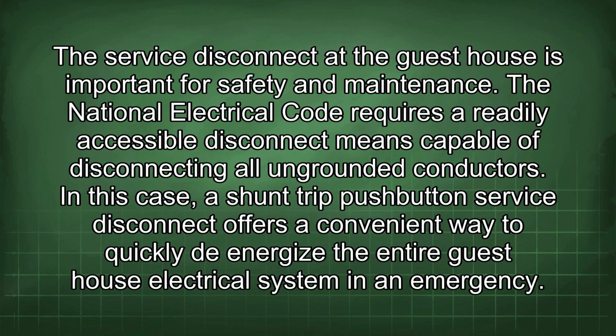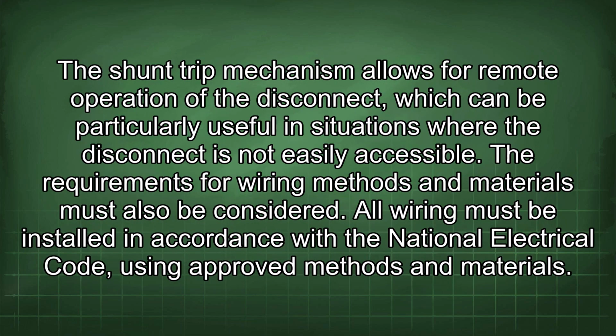The service disconnect at the guest house is important for safety and maintenance. The National Electrical Code requires a readily accessible disconnect means capable of disconnecting all ungrounded conductors. In this case, a shunt trip push-button service disconnect offers a convenient way to quickly de-energize the entire guest house electrical system in an emergency. The shunt trip mechanism allows for remote operation of the disconnect, which can be particularly useful in situations where the disconnect is not easily accessible.